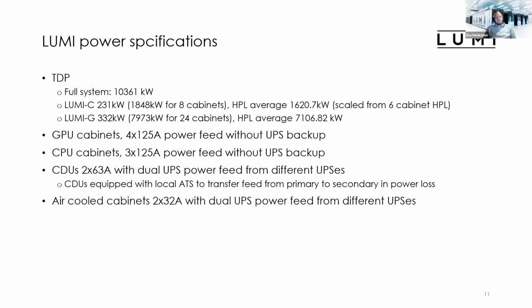So the CDU is equipped with a local ATS to transfer from the primary to the secondary feed in case of power loss. So it's basically always using the primary feed fully, and in case of power failure from the primary, it switches to the secondary to avoid cooling loss in the compute cabinets. All of our air-cooled cabinets have 2 times 32 amp power feeds, and both of those power feeds are UPS backed up from 2 different UPSs. So there is redundancy in place at the UPS level also for these air-cooled cabinets and for the CDUs.